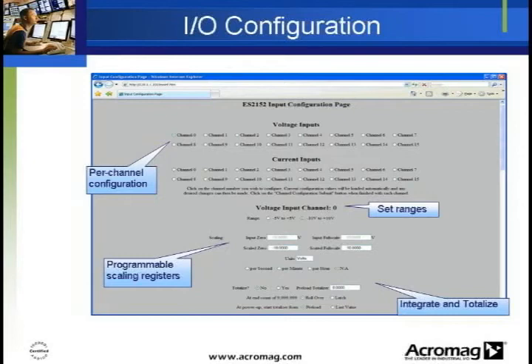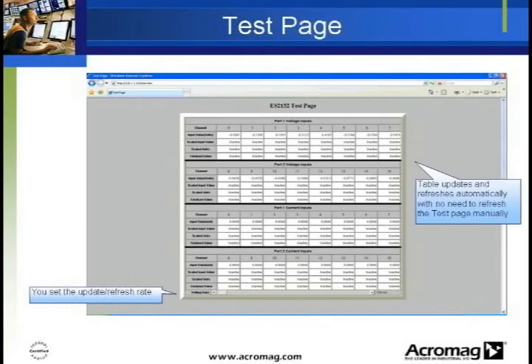Expanding its flexibility, each voltage port or 8-channel group on the EtherStax module can be switched between the 8B standard connection or direct screw terminals via the web configuration tool. The test page shows input values, scaled values in units, and totalized values for each channel in real time to verify that the unit is connected properly and communicating successfully with the network. Channels in the EtherStax test page are updated automatically without refreshing the page to allow live monitoring of sensor values.